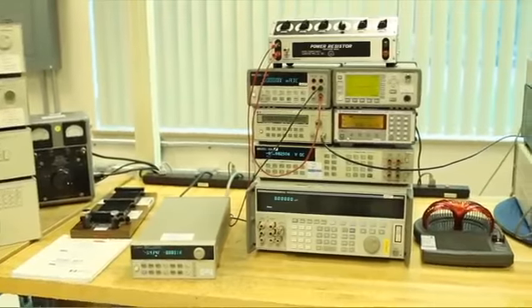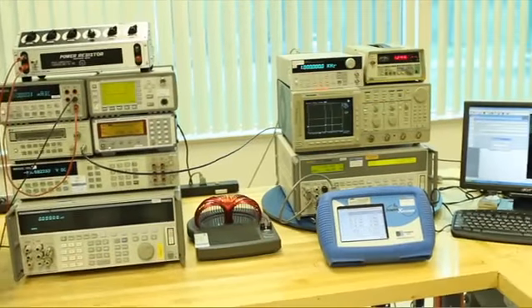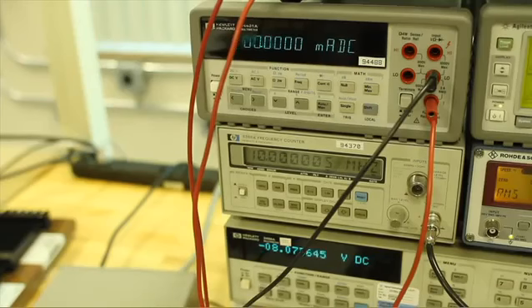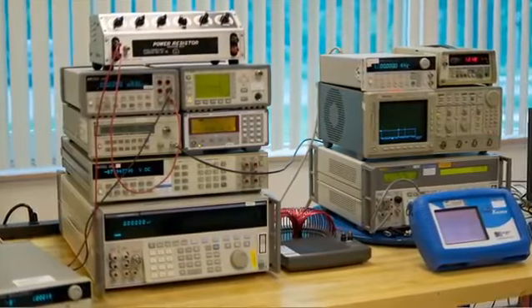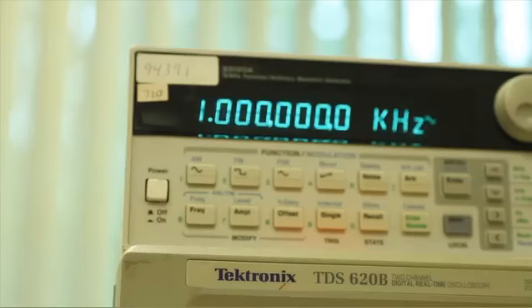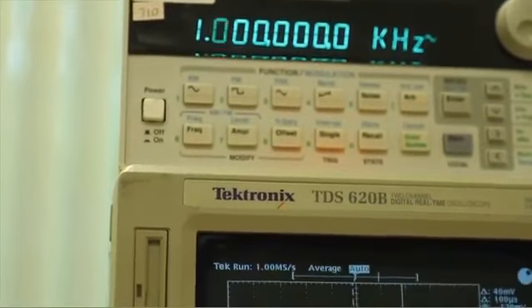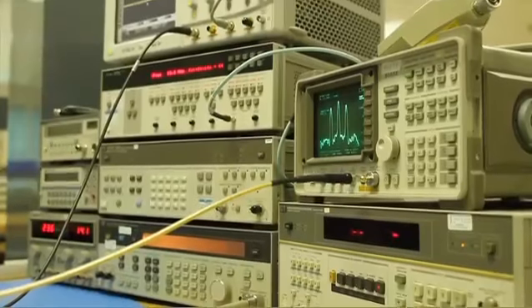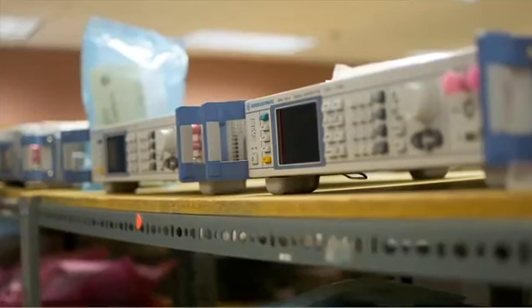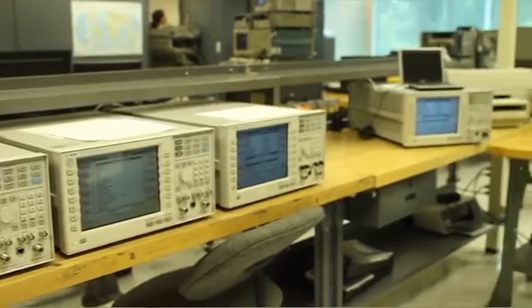Another one of our test stations is the DC low frequency power monitoring station. At that bench we calibrate DC power supplies, AC power supplies, digital voltmeters, low frequency generators, and power monitoring equipment. Our primary customers that I see and talk to that are renting and purchasing a lot of our test gear range dramatically. So you never really know where our equipment is going to show up.